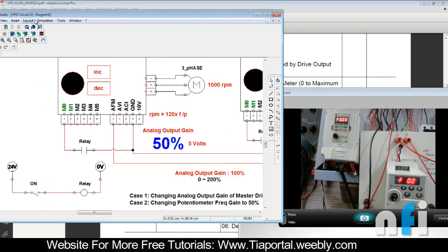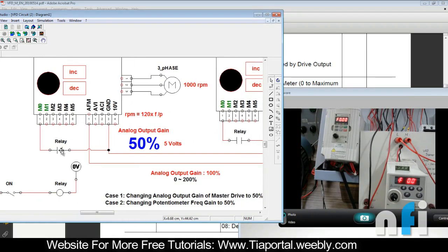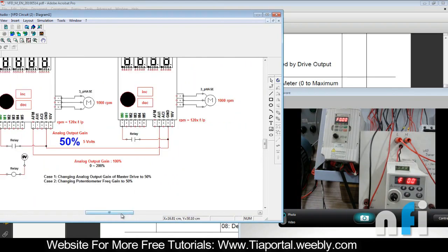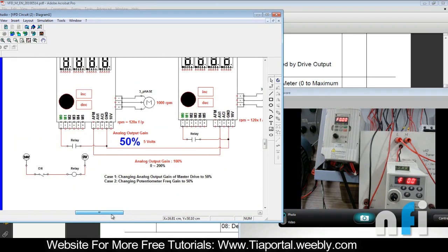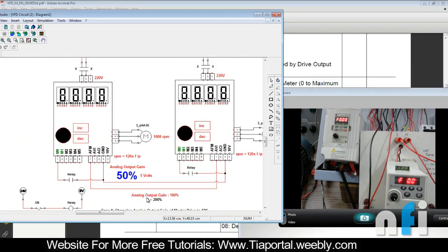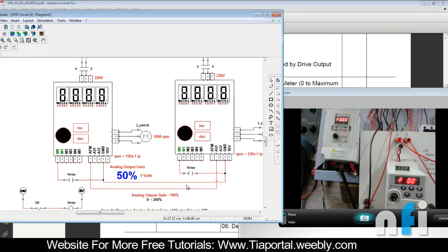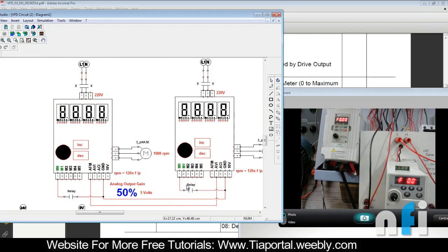Take a relay and a switch — connect the relay with the switch so that when the switch is on, the relay contact closes, shorting the ground and M0 terminal. Connect another contact to short the ground and M0 of the slave drive the same way. That's how you can synchronize the on/off operation as well. This was all about synchronizing the drive using analog output feedback.